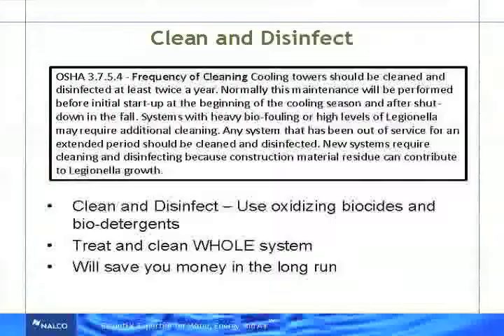Now, clean and disinfect doesn't mean that you just shut the tower down, take a pressure washer to the fill, drain the sump, and maybe vacuum that out a little bit. It means that you should actually clean and disinfect the whole system, which means the application of some oxidizing bleach, bromine, ozone, whatever you're using for your oxidizing biocide. Bump those up a little bit, run it through your whole system. You might want to use some detergents to really clean it up if you want to. It makes the cleanup process afterwards a lot easier if you do that. So make sure that you're actually disinfecting too, not just cleaning the system. And as I said, treat and clean the whole system.